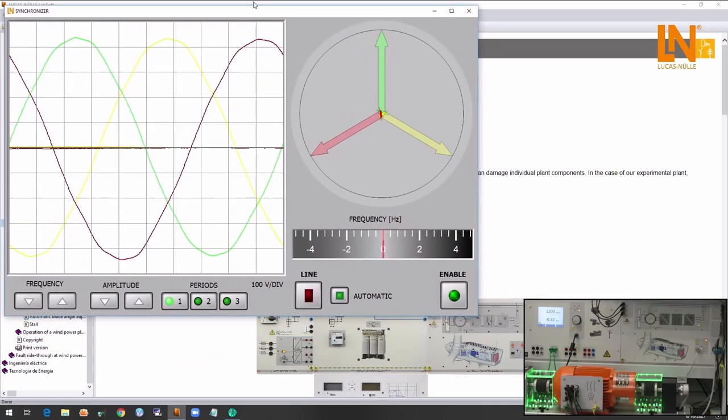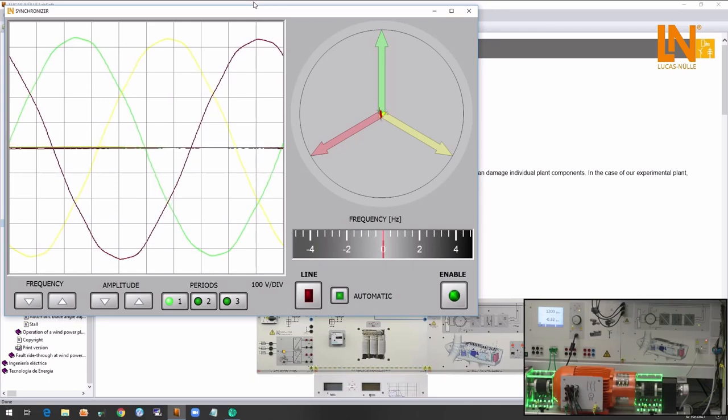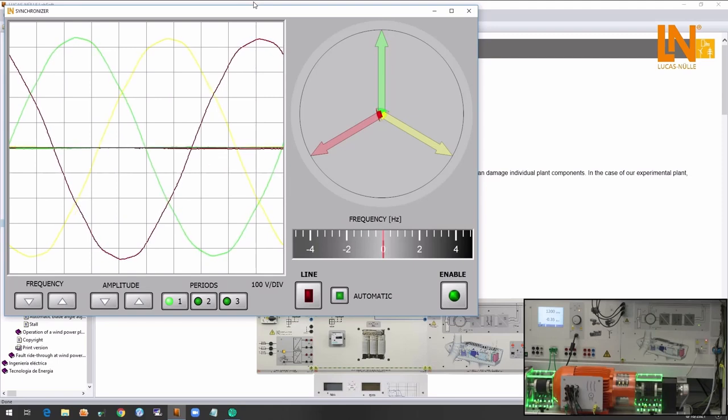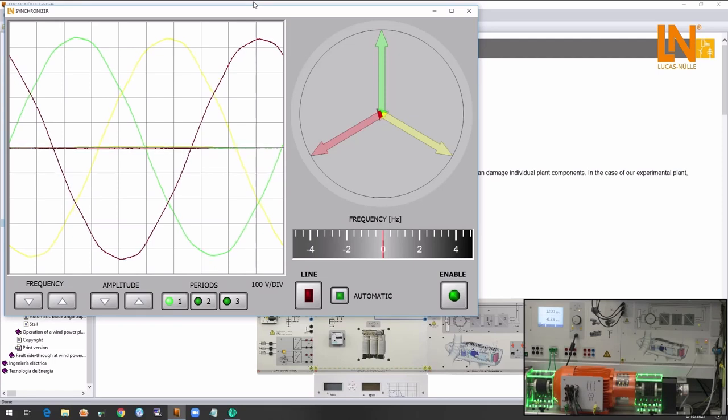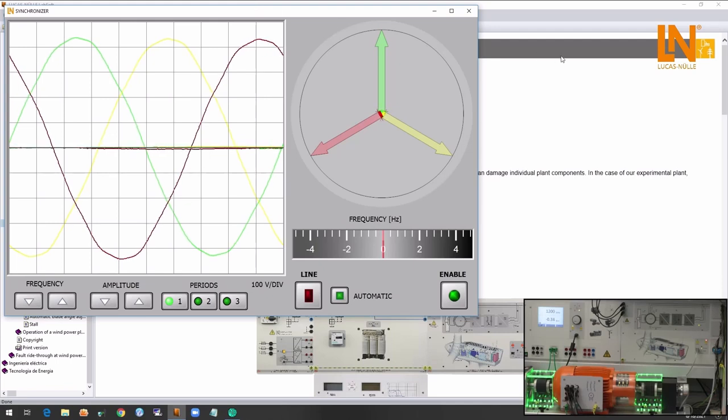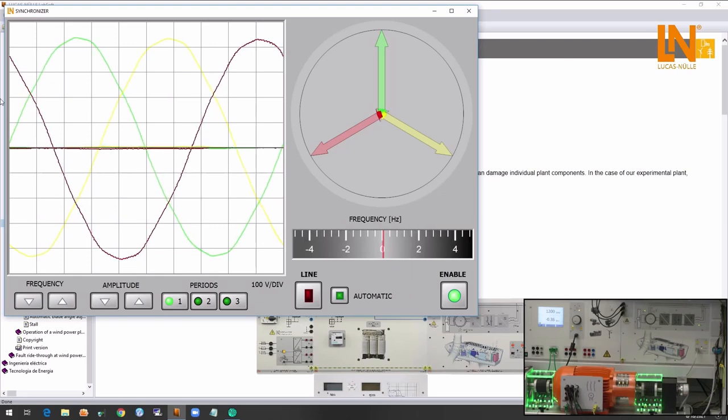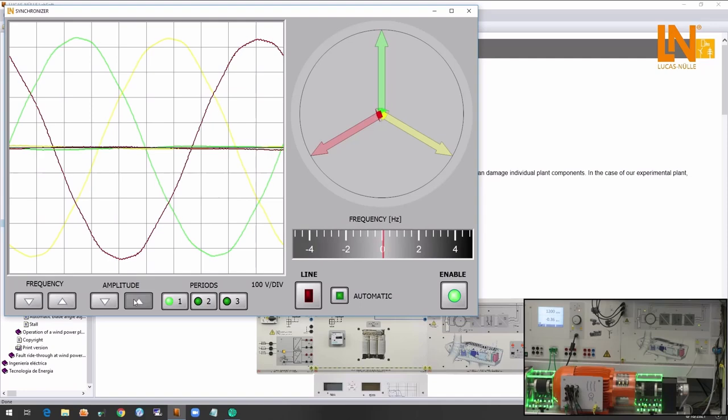You can already see the three phases of the grid that is represented here. We know that for synchronizing to the grid there are conditions that have to be met. These conditions are the frequency, the voltage, the phase angle and the sequence of the grid and the generator that have to be the same.